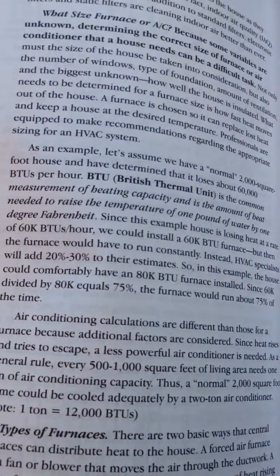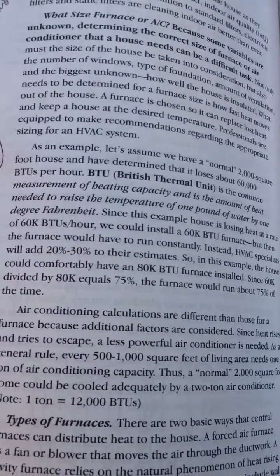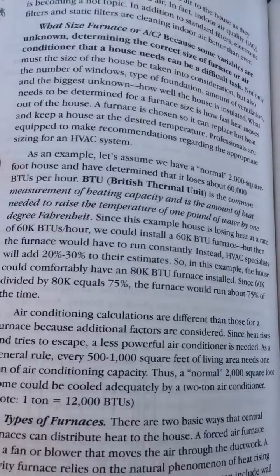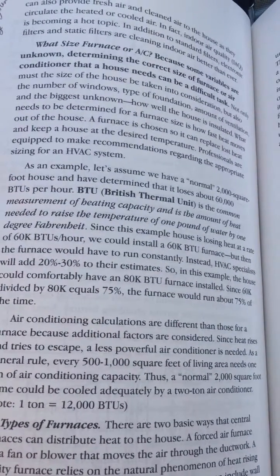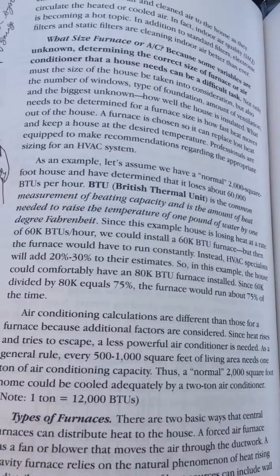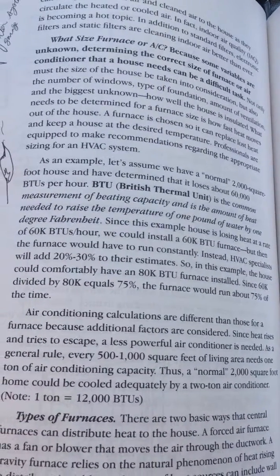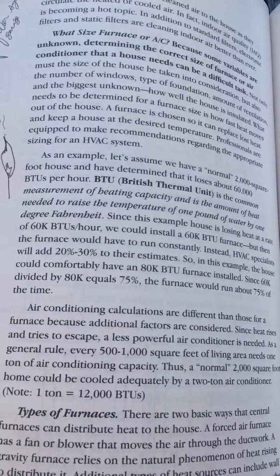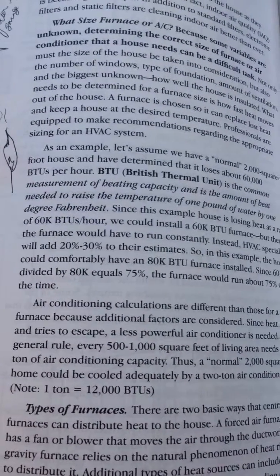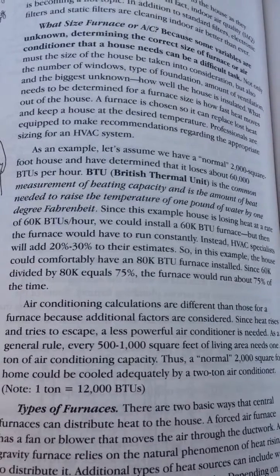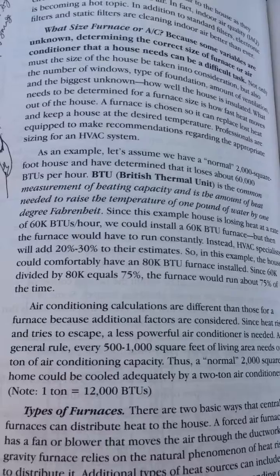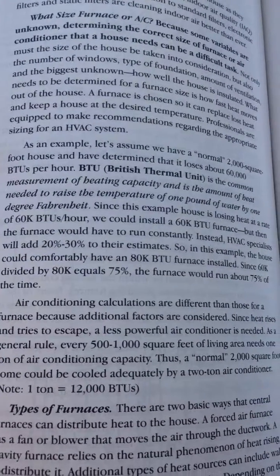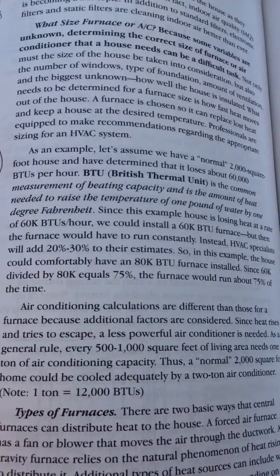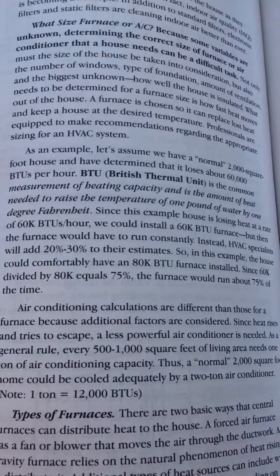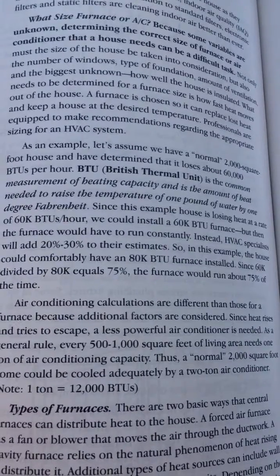Since this example house is losing heat at a rate of 60,000 BTUs an hour, we could install a 60,000 BTU furnace, but then the furnace would have to run constantly. Instead, HVAC specialists will add 20% to 30% to their estimates. So, in this example, the house could comfortably have an 80,000 BTU furnace installed. Since 60,000 divided by 80,000 equals 75%, the furnace would run about 75% of the time.